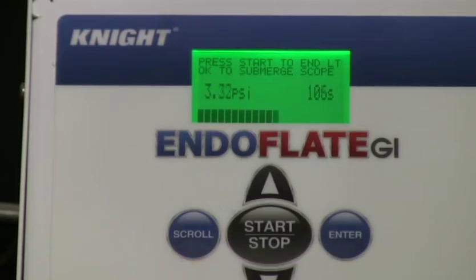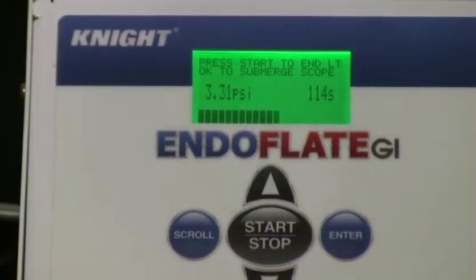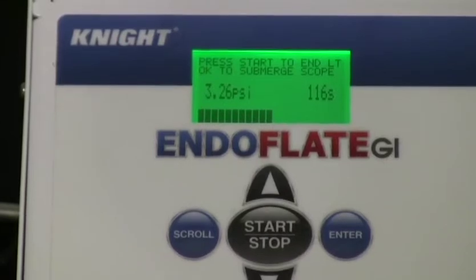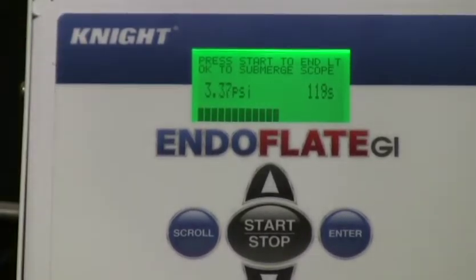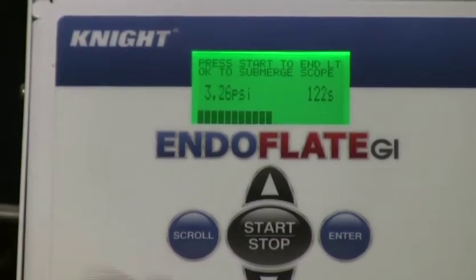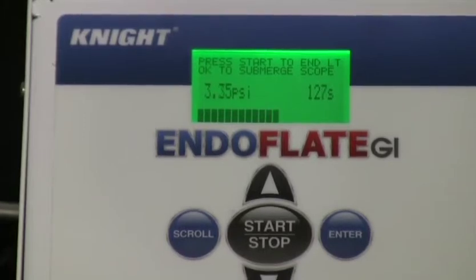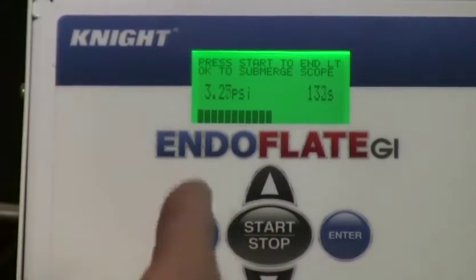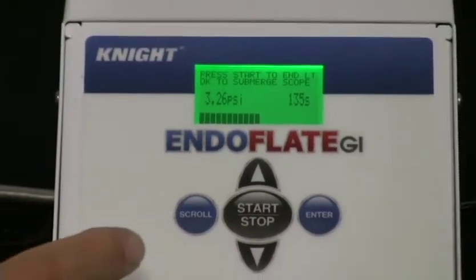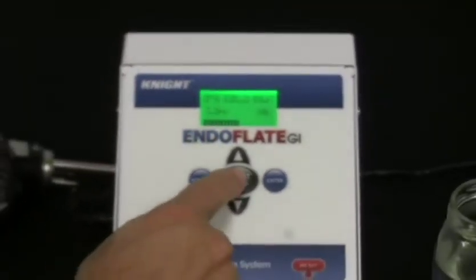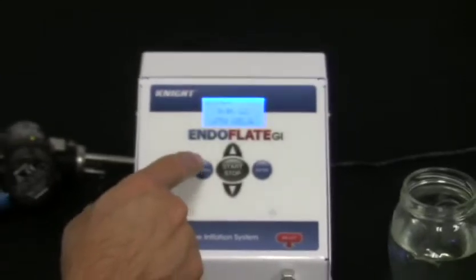So at this point, if I'm the technician, I've been trained, I know I've got a stable pressure, the display is green, I can now take the scope and fully submerge it into the sink. Once I do that, I do a full inspection over the scope, looking for bubbles. I don't see any. Okay, that particular scope does pass the leak test and I can begin my manual cleaning. And to disconnect and end the leak test, all they have to do is press the start button again, and you'll hear a little psst sound. That's the three-way valve relieving the internal pressure of the inflation on the scope. Okay, and now we've finished.